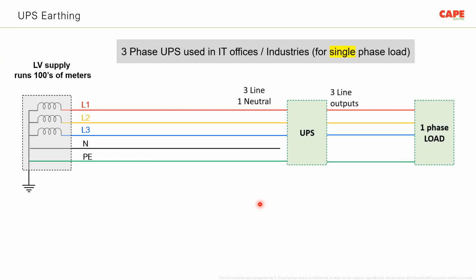But in office and industrial premises, we often have single-phase loads, especially computer load. So what people do is they use a UPS with 3-phase input and 3-phase output, and take the neutral of the transformer and share it to the load. The common neutral, which is coming from the input, is taken and connected to the single-phase load. Now this circuit itself is totally a disaster.